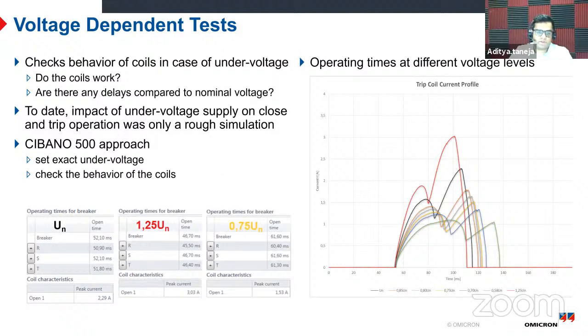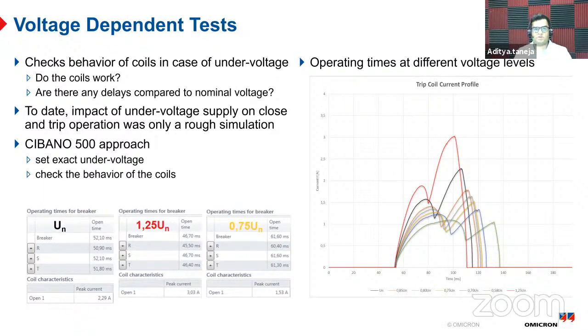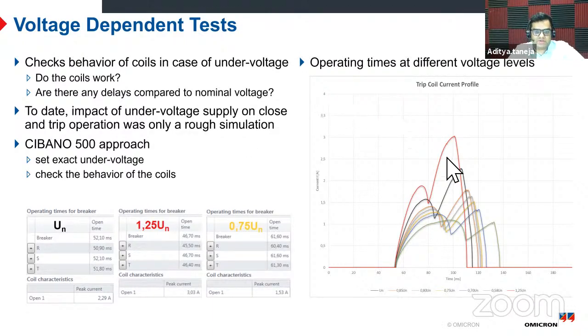Yeah, I just want to emphasize this point again. I cannot stress it more that trip coil and close coil are very important. They fail a lot. They are very weak as compared to the gigantic breaker, which is very rugged. If they fail, the relay command will not operate the breaker, and that's a sorry situation. And you would not like to be caught in that situation. So better to have this test and make sure it works in under voltage condition. This will definitely show you if there are any problems. Sometimes in 380 kV breakers, there are separate coils for each phase, and you just, oh, sorry.